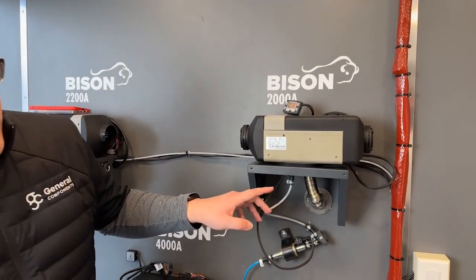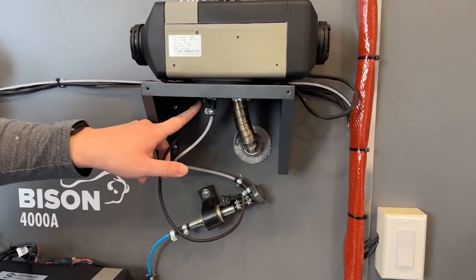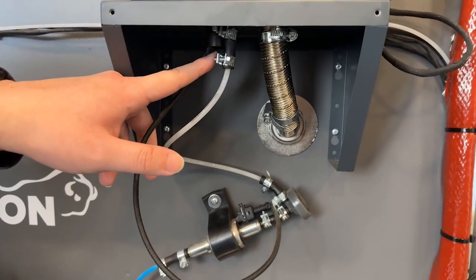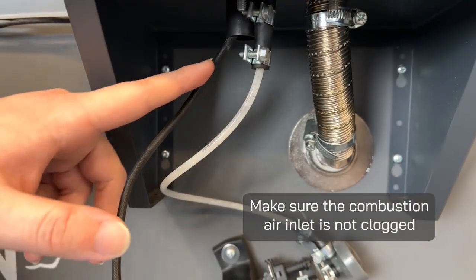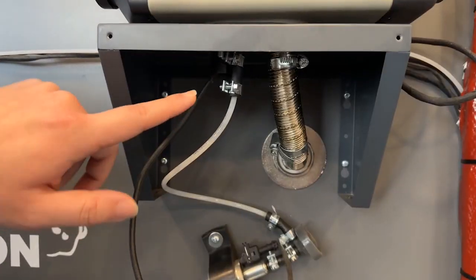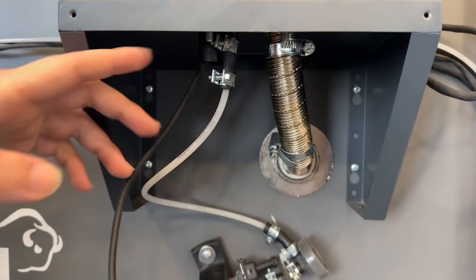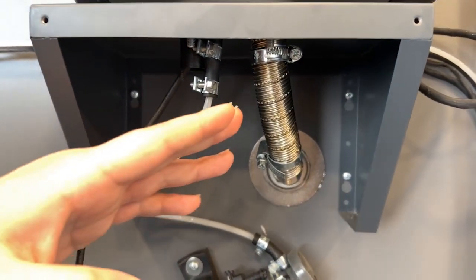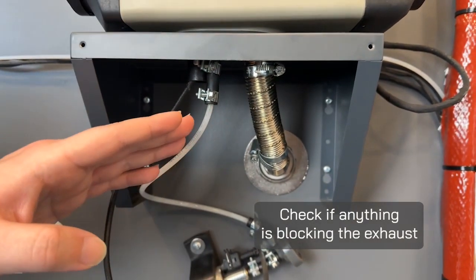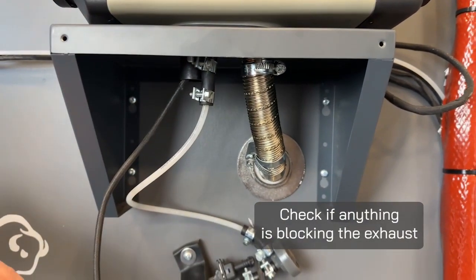And as many of you know, in order for combustion to happen, we need 3 major components. One is air, second is fuel, and third one is spark. Let's look at the first component, the air component. So down here, this black pipe is the combustion air inlet, and let's make sure it is not clogged. After we check the intake, and if the intake is free, we will now check the exhaust to see if anything is blocking the flow out of the heater.